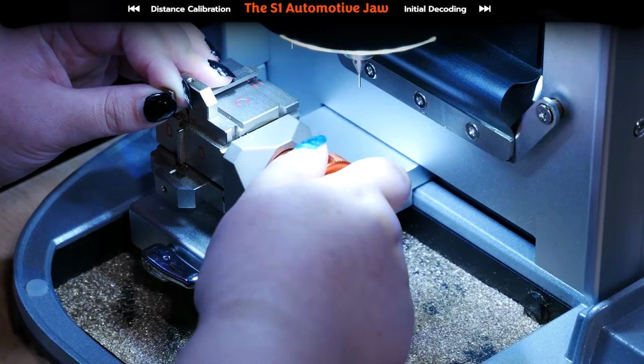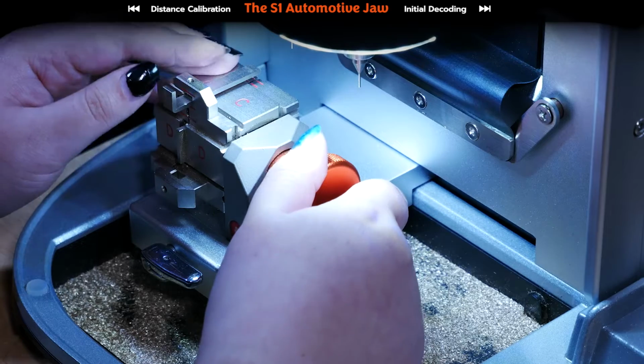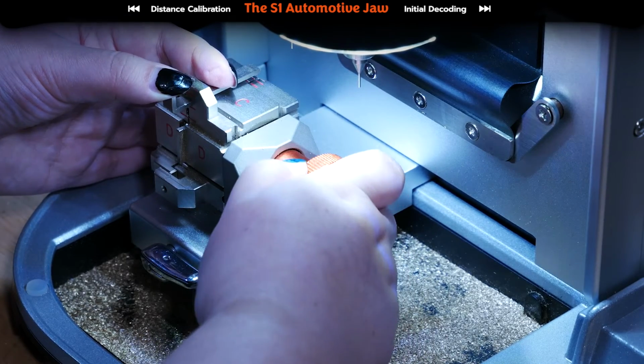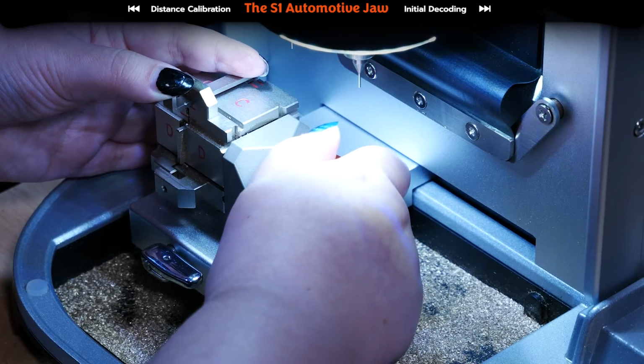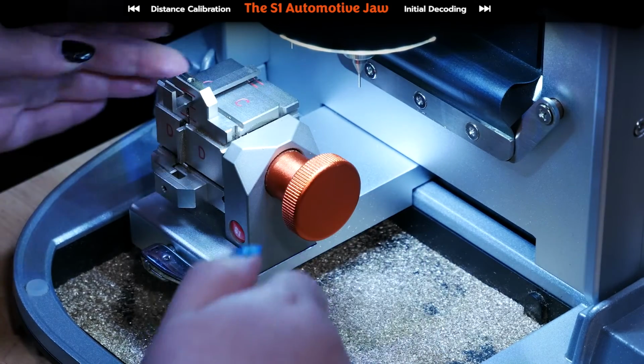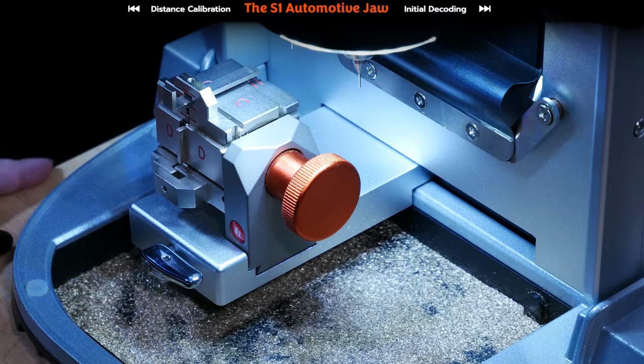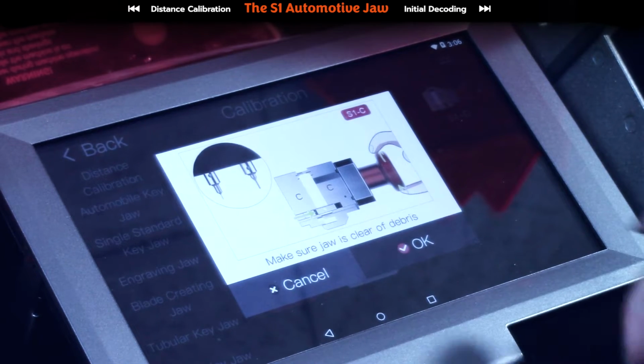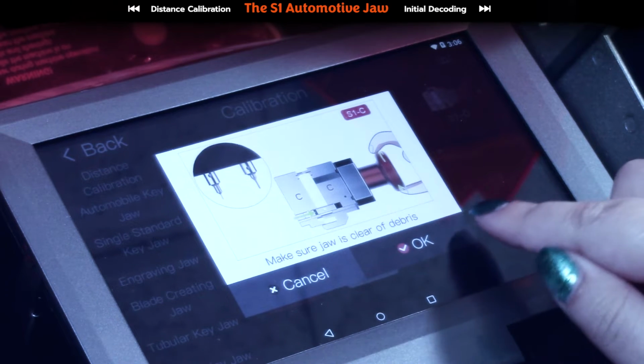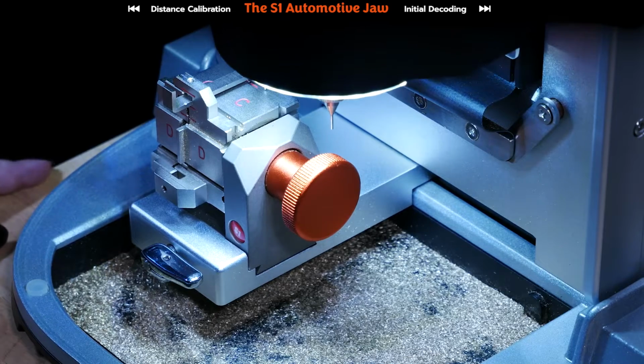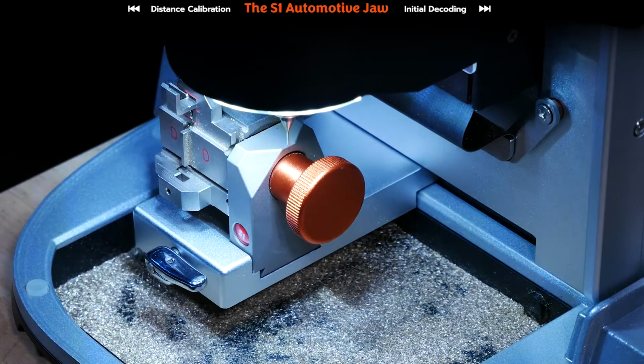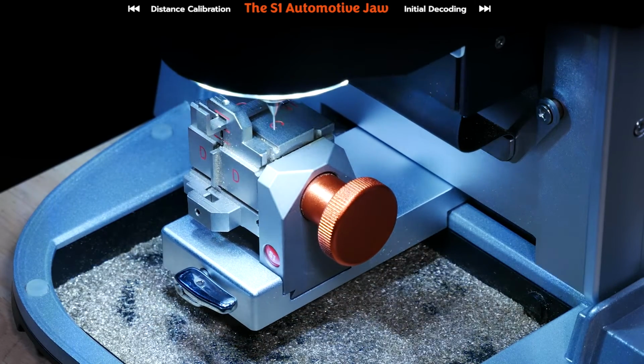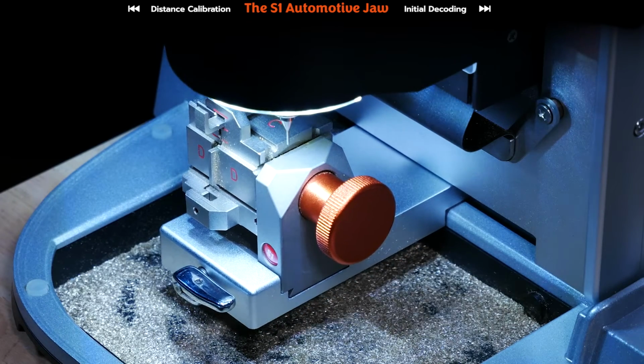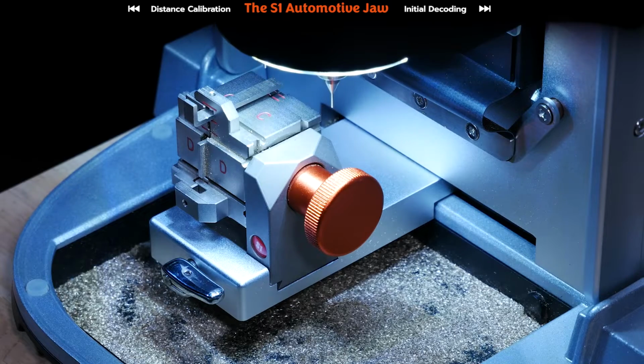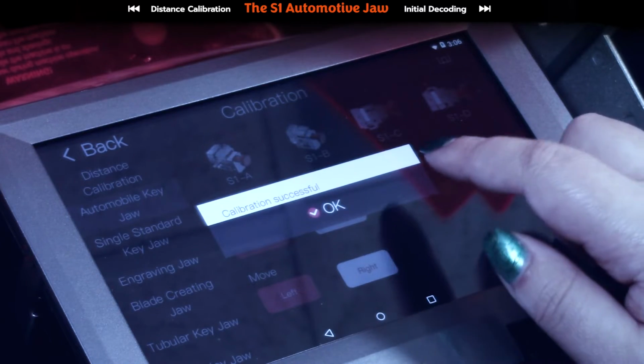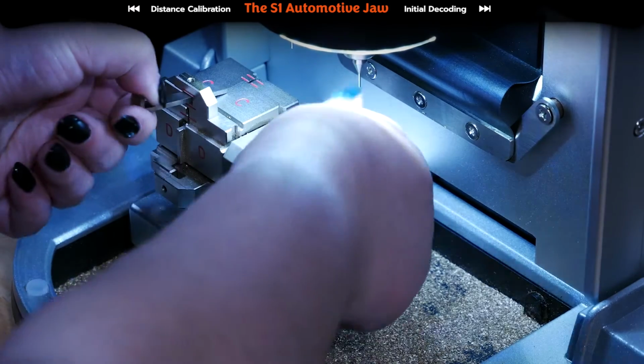Now, it doesn't have to be exact, but you do want to get it as close as possible. And at the same time, you do want to try to get it as leveled as you can. That way, it is not crooked in the jaw. And once it looks pretty good there, you can go ahead and get it tightened in nice and good with the orange knob. Go back up to your screen. Make sure your jaw is clear of debris, it's fine, and hit OK. Calibration successful, hit OK. And now we're going to go over to the S1B side.